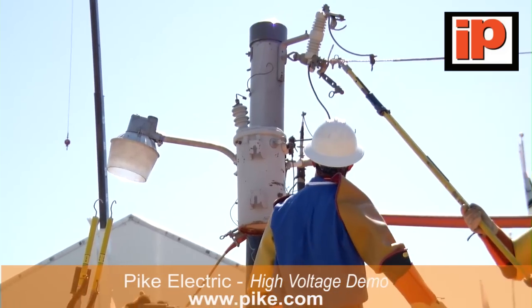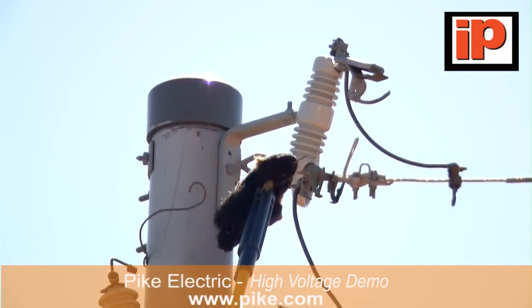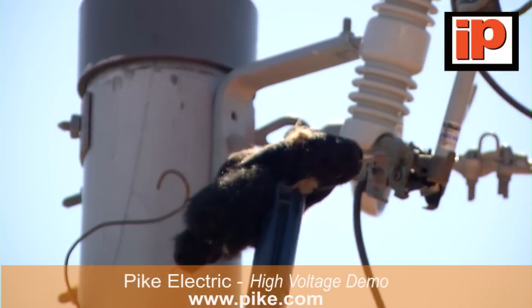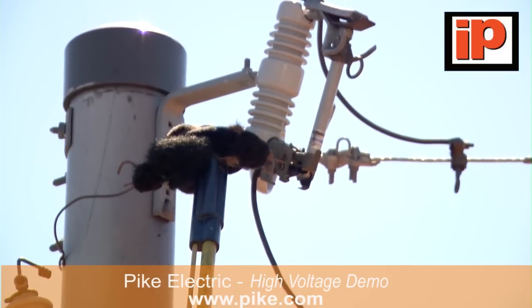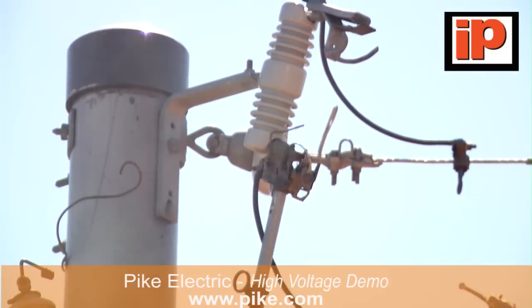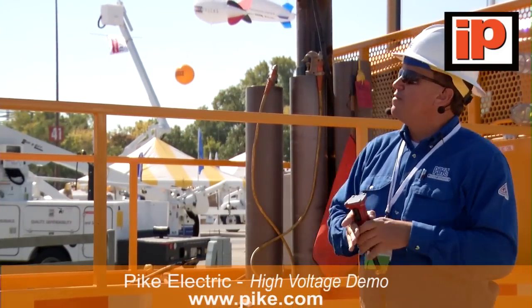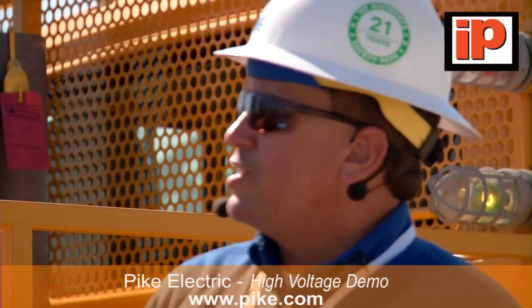A problem that power companies and co-ops have is animals getting on top of transformers and knocking out the line. We have Sammy the squirrel here today. He's going to show you what happens when a squirrel or an animal makes contact with an energized transformer — there's going to be a loud noise, so prepare yourself. A lot of people, when they hear that noise, automatically think their transformer blew up. Actually, it's a fuse — there's a fault on that transformer and that fuse will blow. The lineman comes out, re-fuses the transformer, and gets the power back on.